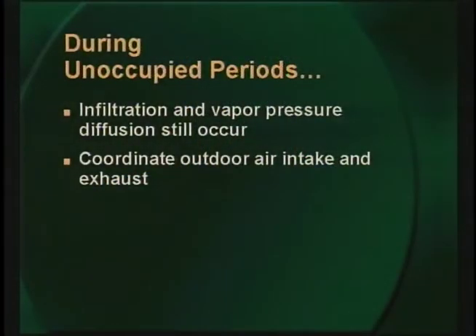It's important to recognize that moisture enters buildings around the clock. Some of the moisture sources leave the building when the occupants leave, but not all of them. Significant amounts of moisture can be drawn into a building while it's unoccupied if the building pressure is not controlled. A common scenario is a school that shuts down unit ventilators shortly after students leave, yet bathroom, locker room, and kitchen exhaust fans continue to operate for hours, creating negative building pressure. This has driven many designers to monitor relative humidity levels during the unoccupied period and operate the HVAC system to maintain humidity below a preset limit, usually 60%.